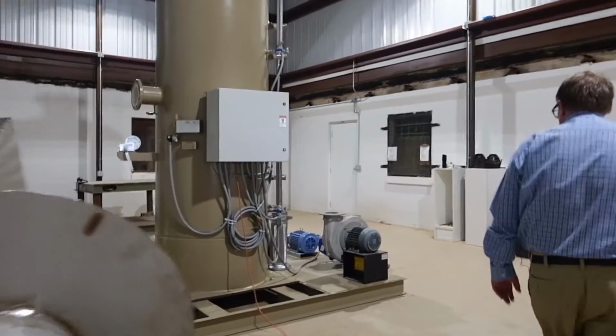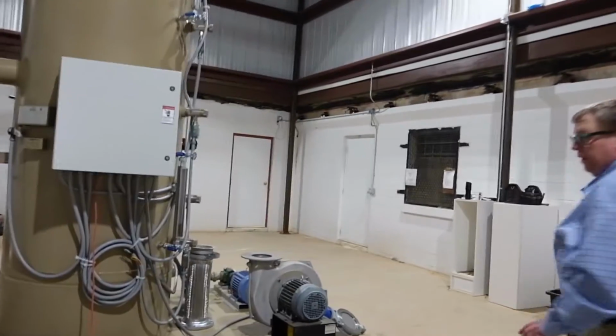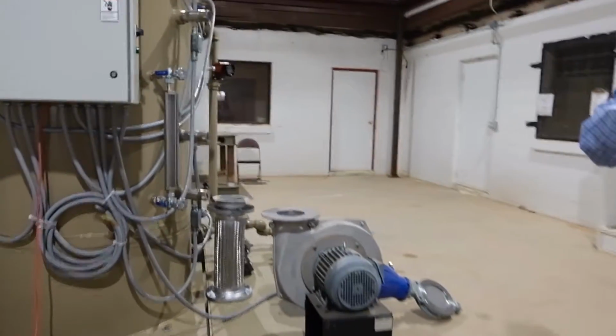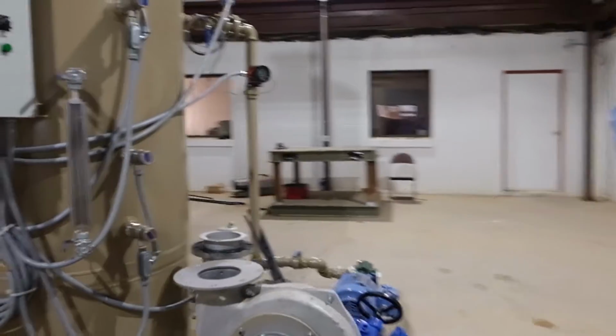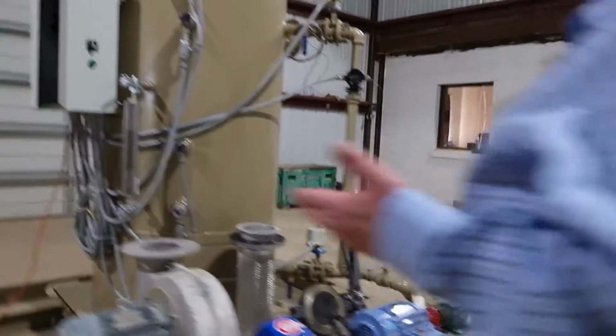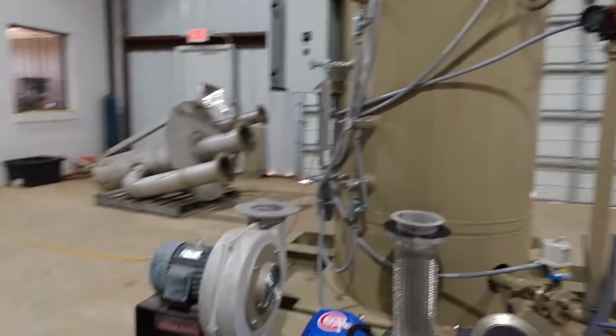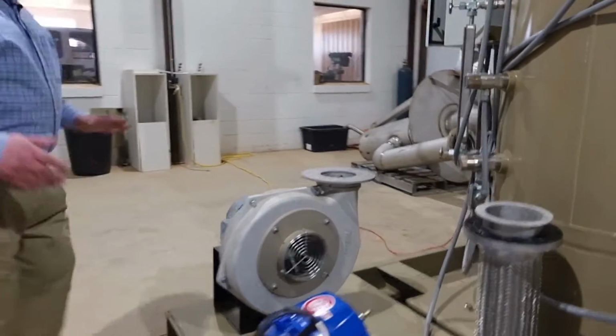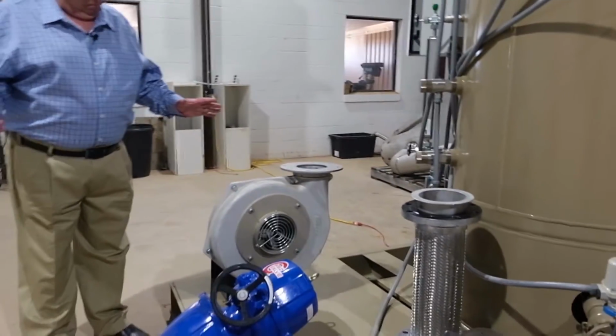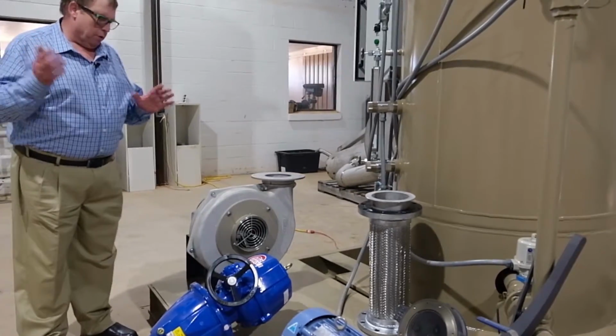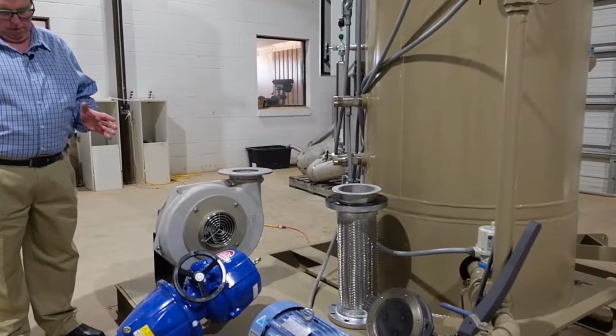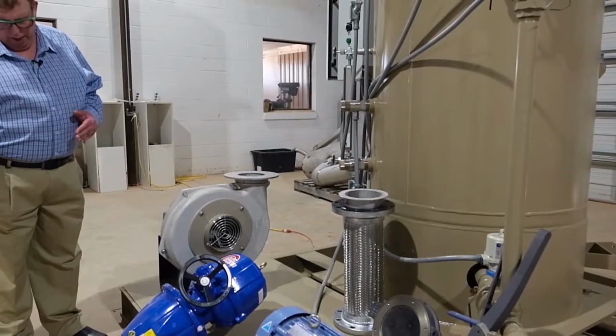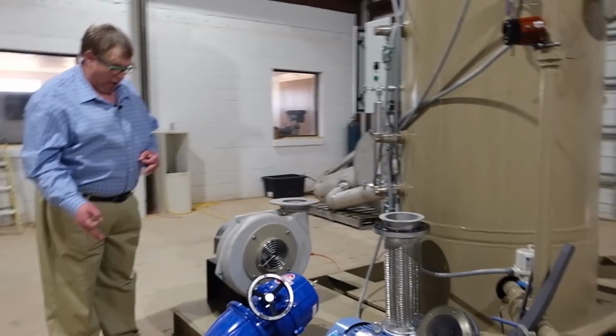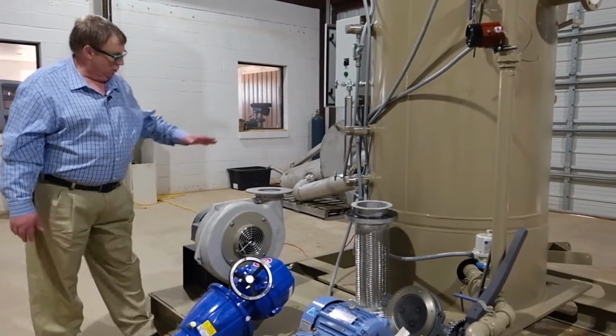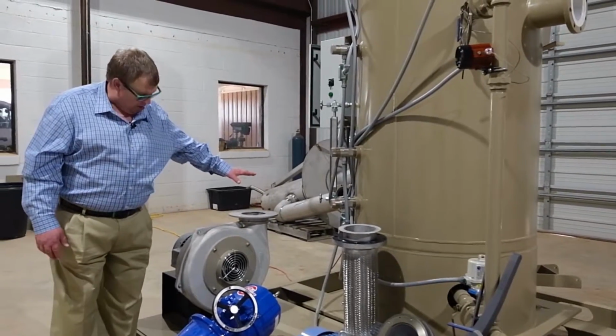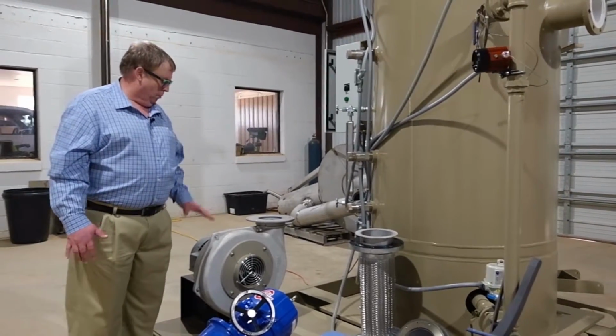Coming back over here to the blower feature on this flare, because we've added oxygen to the flare, it's going to require that we add some safety features. This is a spring fail close, high performance, graphite packed, fireproof butterfly valve, and it positions itself just downstream the outlet of the blower.